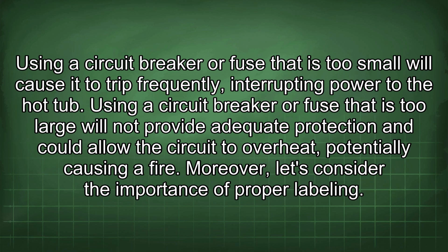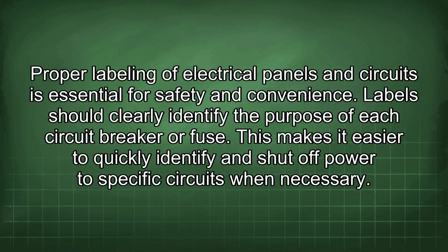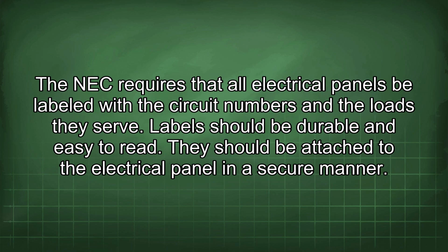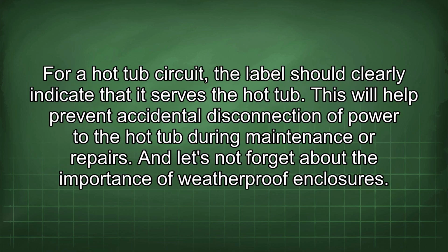Moreover, let's consider the importance of proper labeling. Proper labeling of electrical panels and circuits is essential for safety and convenience. Labels should clearly identify the purpose of each circuit breaker or fuse. This makes it easier to quickly identify and shut off power to specific circuits when necessary. The NEC requires that all electrical panels be labeled with the circuit numbers and the loads they serve. Labels should be durable and easy to read. They should be attached to the electrical panel in a secure manner. For a hot tub circuit, the label should clearly indicate that it serves the hot tub. This will help prevent accidental disconnection of power to the hot tub during maintenance or repairs.